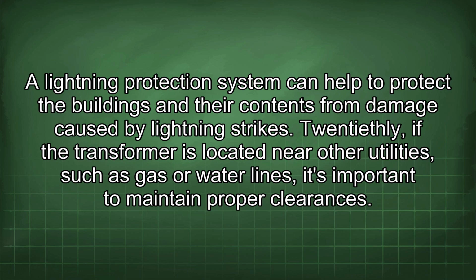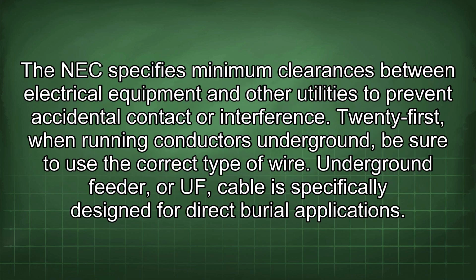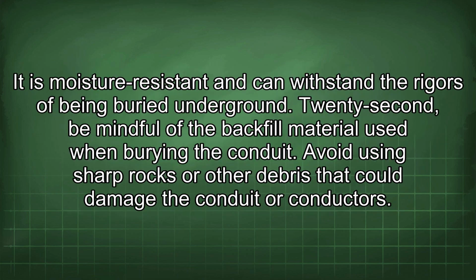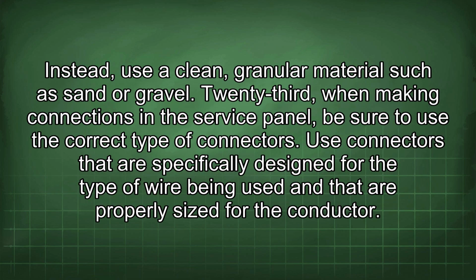20thly, if the transformer is located near other utilities such as gas or water lines, it's important to maintain proper clearances. The NEC specifies minimum clearances between electrical equipment and other utilities to prevent accidental contact or interference. 21st, when running conductors underground, be sure to use the correct type of wire. Underground feeder or UF cable is specifically designed for direct burial applications. It is moisture resistant and can withstand the rigors of being buried underground. 22nd, be mindful of the backfill material used when burying the conduit. Avoid using sharp rocks or other debris that could damage the conduit or conductors. Instead, use a clean, granular material such as sand or gravel.